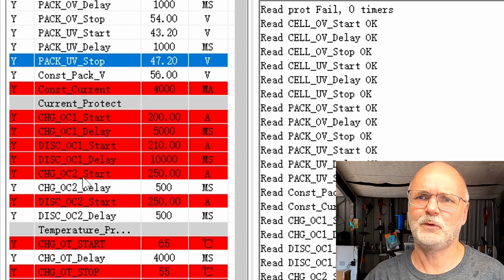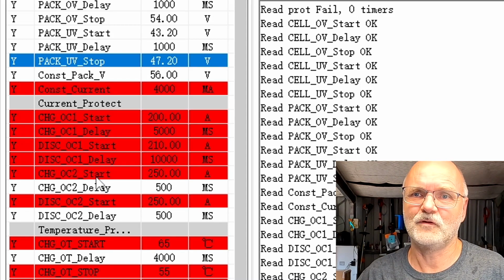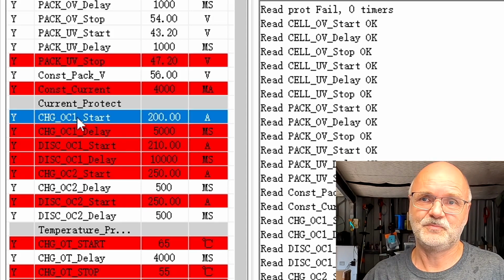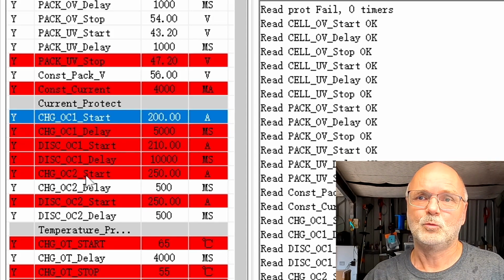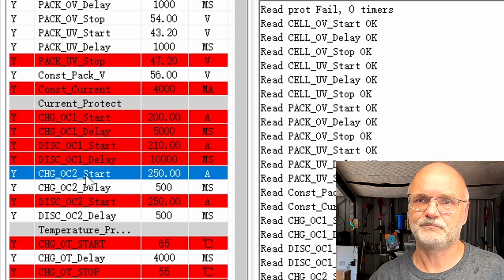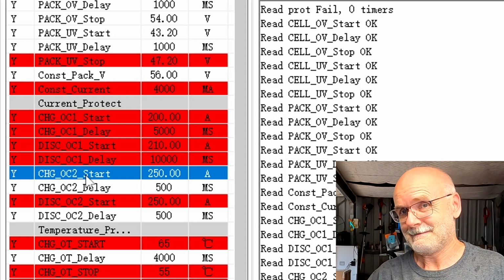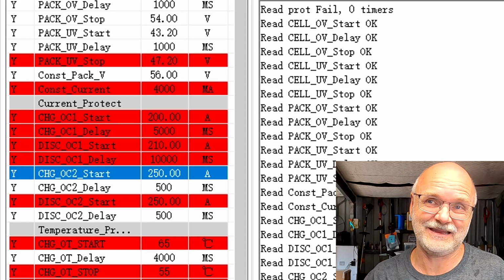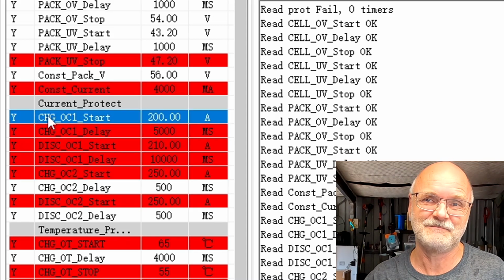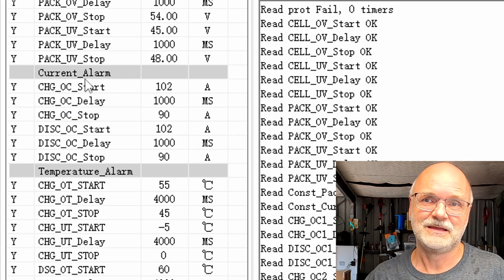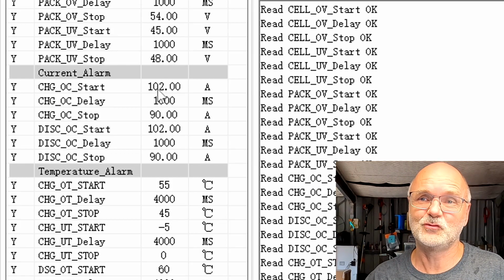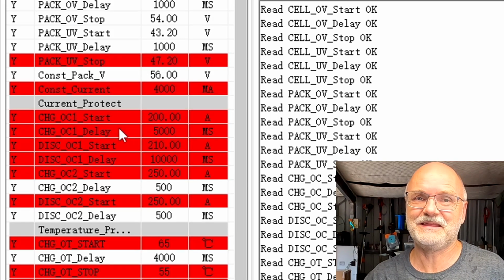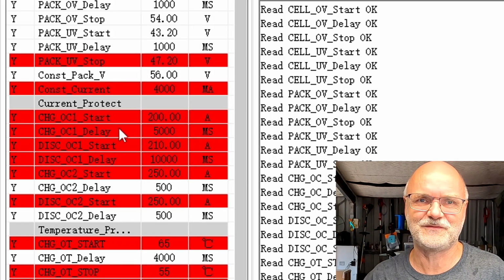And I was asking the question, why do we have 2 parameters for starting the overcurrent protection? Apparently this parameter here is just an alarm, while number 2 is when it actually triggers and turns off your BMS. So I was asking again, why do we have an alarm tab here if one of the alarms is already displayed under the protection? Because if we have a quick look in alarm, we can see there's also a charge over current start, which is on 102 amps. And again, I have not received the answer yet.